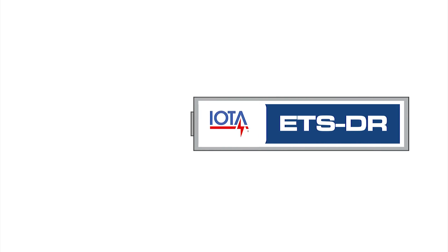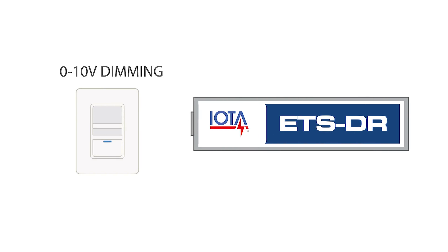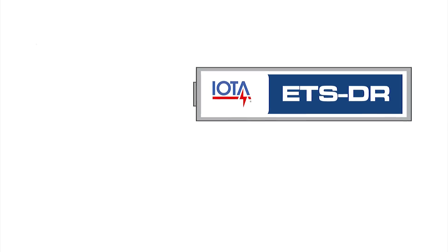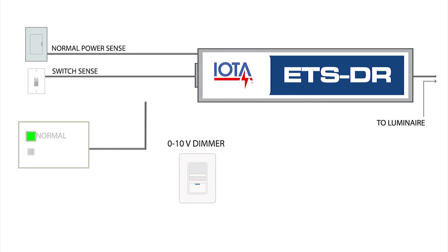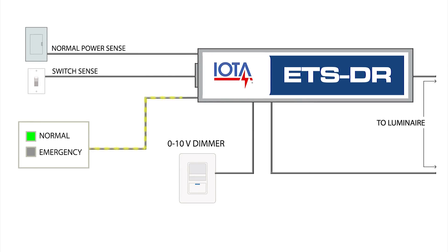Additionally, the ETSDR features unique dimming relays for interfacing with 0-10 volt dimming controls. During normal power conditions, the ETSDR allows the 0-10 volt dimming signal to control your luminaire.